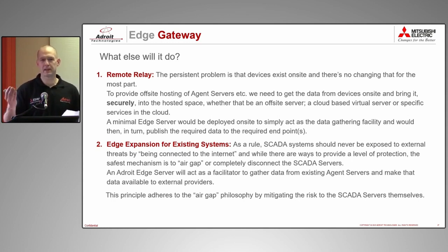It conforms to that idea of an air gap principle in network design. That server is the one that is ultimately talking to the cloud providers, while your SCADA network is totally secure behind your firewalls. So there's no direct communication between your agent servers and the internet. That is key in how this works.